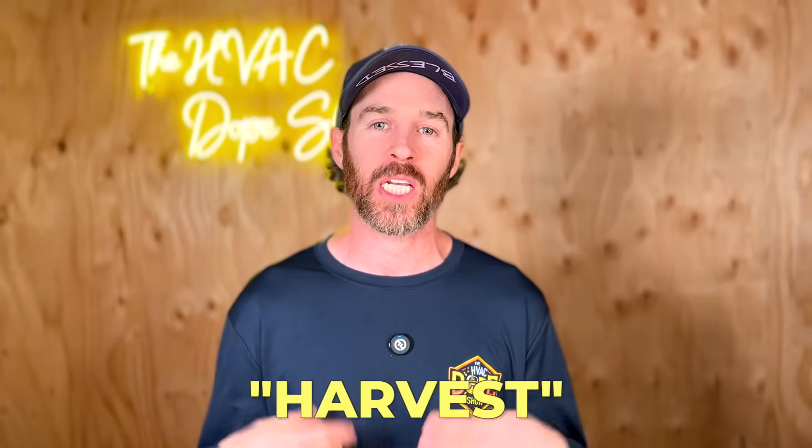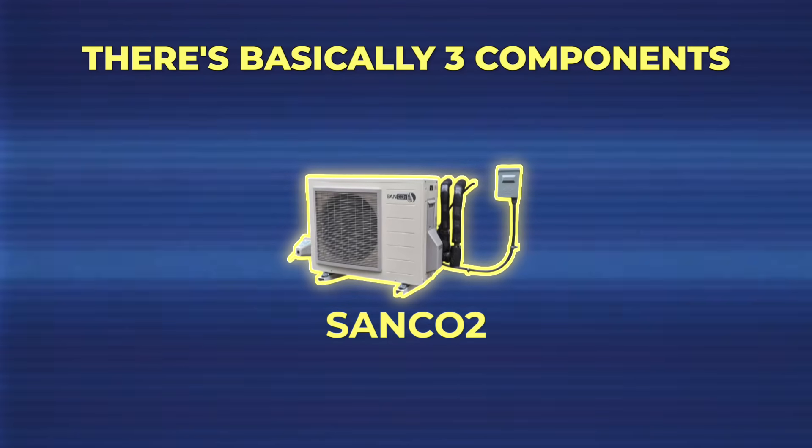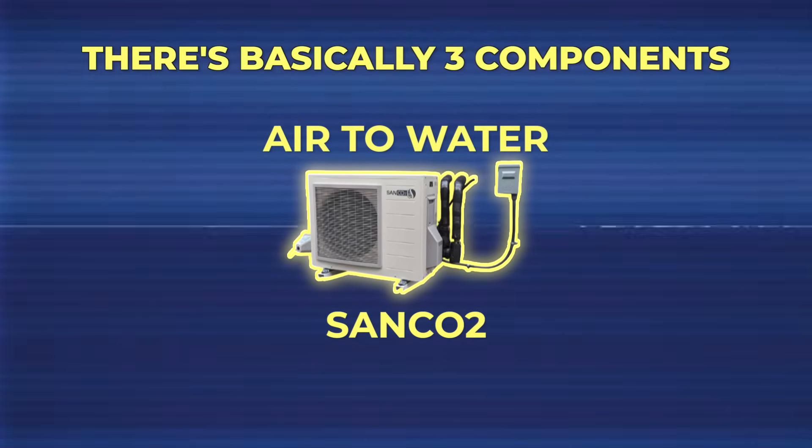The reason this system has the name 'Harvest' is because of three components. First is the outdoor unit — the SANCO2 heat pump water heater, an air-to-water heat pump that heats hot water and transfers it to a storage tank. That storage tank acts as your thermal battery, storing heat in the form of 150-degree potable water.